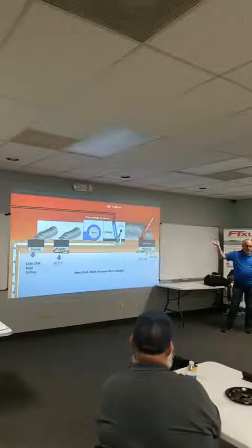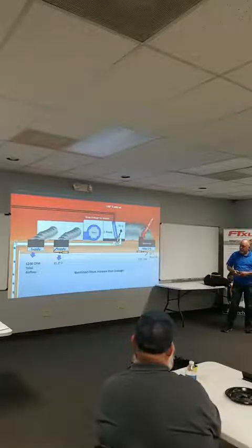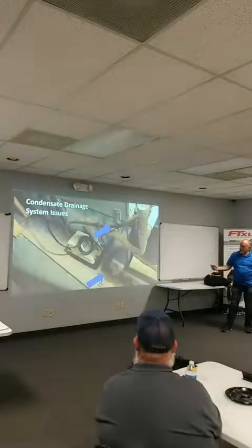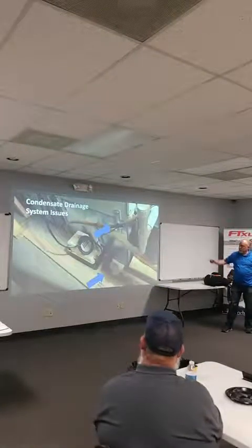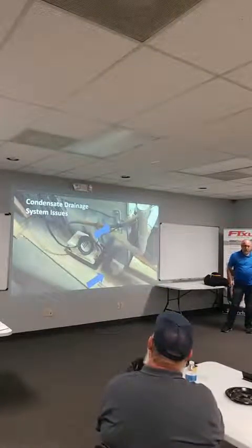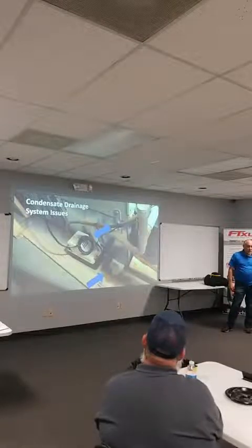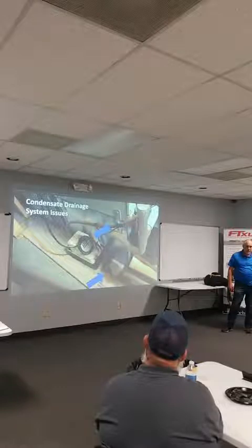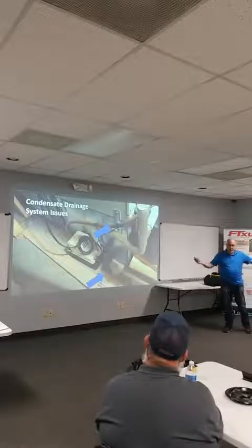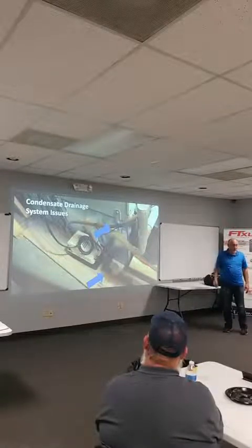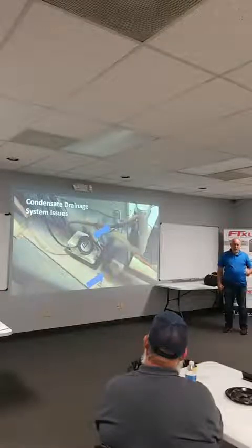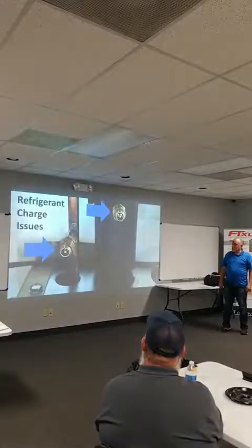If you're putting your probes in the wrong location and you're not taking into account your mixed air temperature in there, you're missing opportunities there, you're missing problems. Condensate drains, when you start seeing this stuff here, that condensate should be clear. That's the same thing with natural gas condensate. If you're on a condensing appliance, it's not dirty either, right? We don't have dirty water coming out of that. When you start seeing that dirty there, we're getting dirt bypass the filter or something's wrong with combustion. These are flags you guys need to be looking for, right?